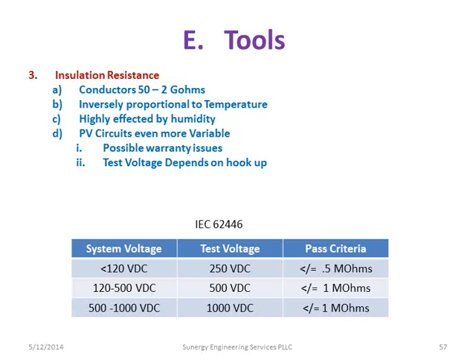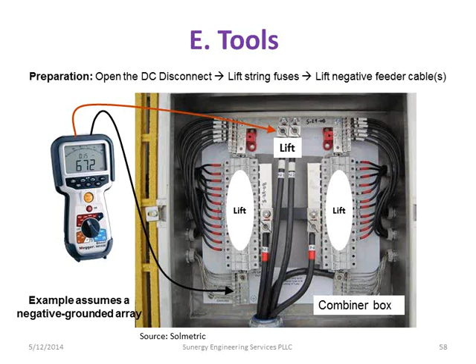So that's actually a really good table as a recommendation. I don't think you have to test modules much higher than what the rated voltage is. And of course, if you've got a big system with a lot of combiners going on, it's pretty easy with all these tools to make a connection to your negative and to your positive bus and just put down each one of your string fuses, one at a time, and do your tests. So you can test very large systems very quickly with all these tools.